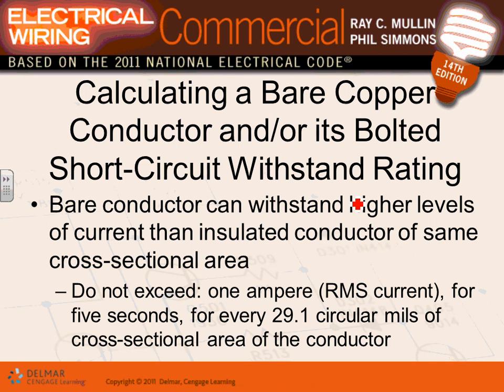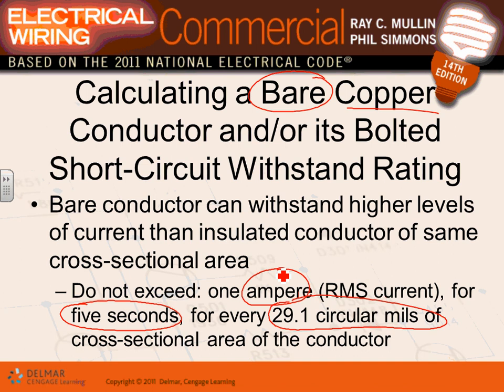Okay. For conductors, if you have a bare conductor, guys, in order to find how much current that conductor can handle, here's the rule that they use, and you guys don't need to know that because we have software. For 5 seconds, remember that magic number, 5 seconds? Every 29.1 circular mils can handle 1 amp for 5 seconds. So take the circular mils of your conductor and divide by 29.1. That will get you how many amps this conductor can handle for 5 seconds. For example, if I have a 5,000 kcmil, divide this baby by 29.1.